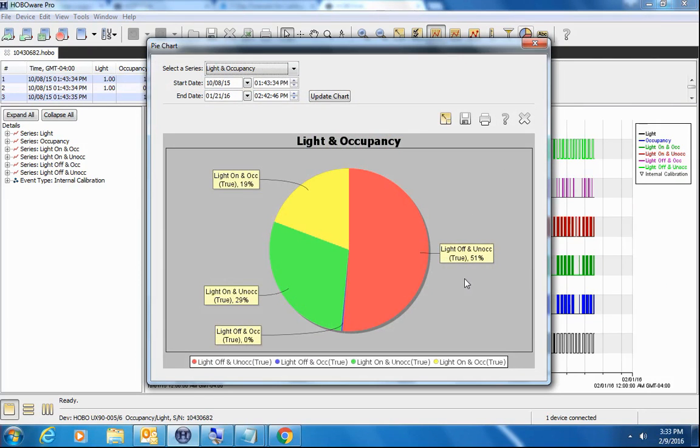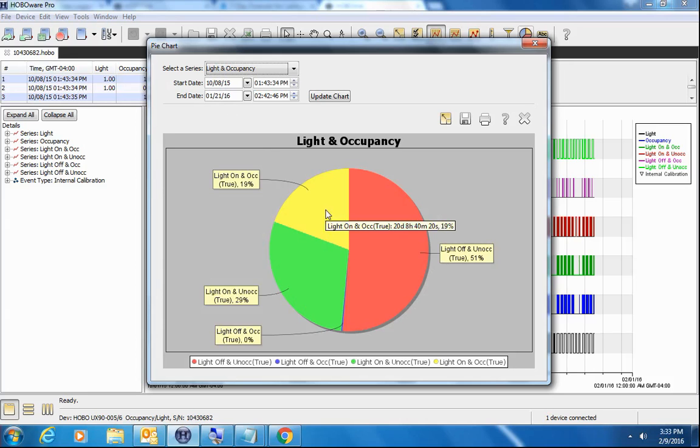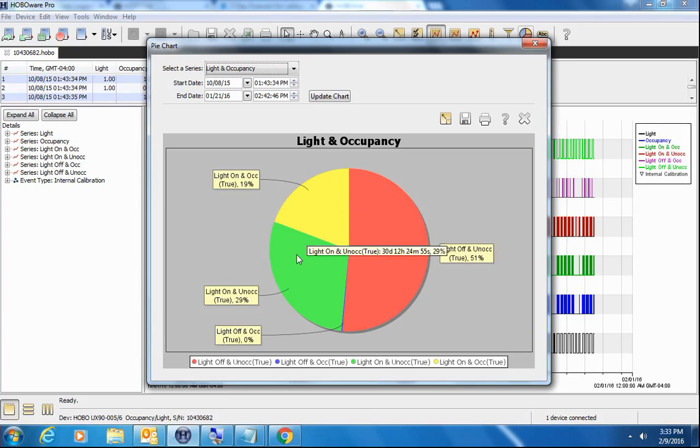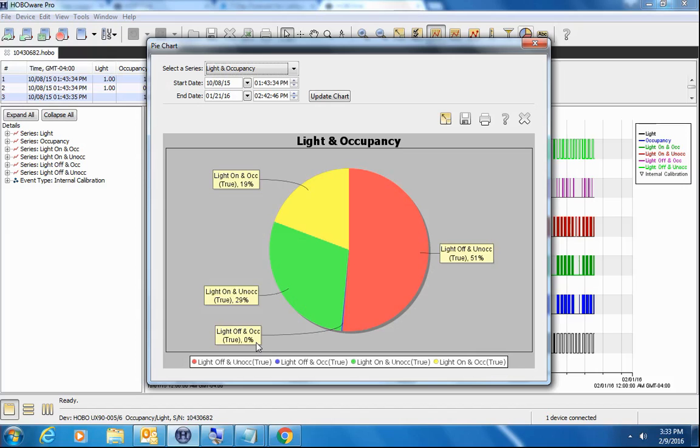We can see that 51% of our time during this deployment, the lights were off and the space was unoccupied. 19% of the time the lights were on and the space was occupied. Again, this is 24 hour, seven day a week data. We can see that 29% of the time the lights were on and the space was unoccupied. And there was no time that the lights were off and it was occupied.